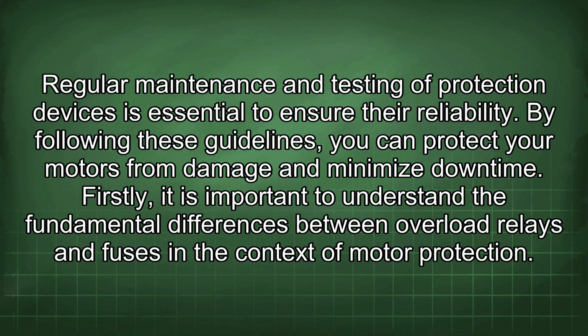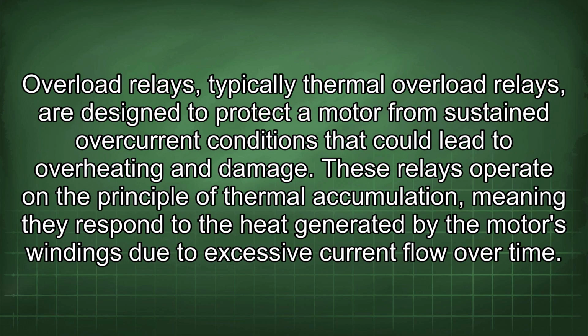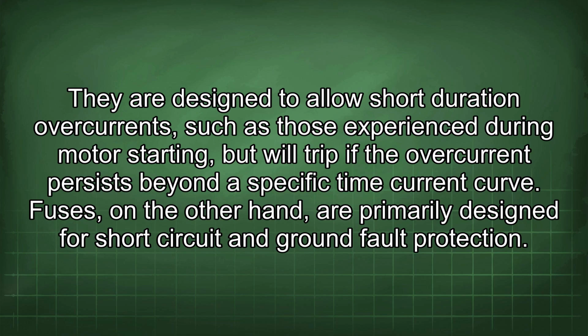Firstly, it is important to understand the fundamental differences between overload relays and fuses in the context of motor protection. Overload relays, typically thermal overload relays, are designed to protect a motor from sustained overcurrent conditions that could lead to overheating and damage. These relays operate on the principle of thermal accumulation, meaning they respond to the heat generated by the motor's windings due to excessive current flow over time. They are designed to allow short-duration overcurrents, such as those experienced during motor starting, but will trip if the overcurrent persists beyond a specific time-current curve.